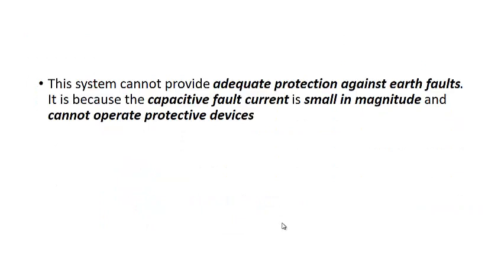This is one of the disadvantages. The last one is that the system cannot provide adequate protection against the earth fault. As I have told you, it is because the capacitive fault current is small in magnitude and cannot operate the protective devices. Because these currents cannot be detected successfully, the current should be very high so as to detect the earth fault. And ideally, you will see these currents we actually neglect with respect to load as well. Since I told you it is 4 ampere, in case of load, it may be of the order of hundreds of amperes.